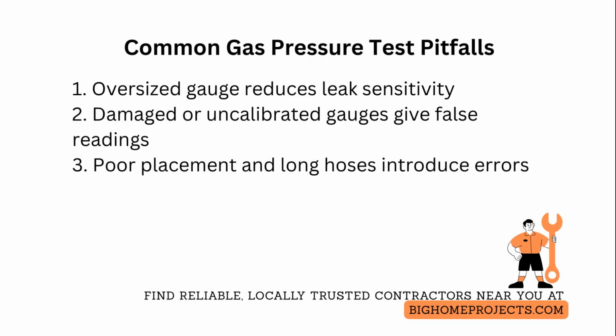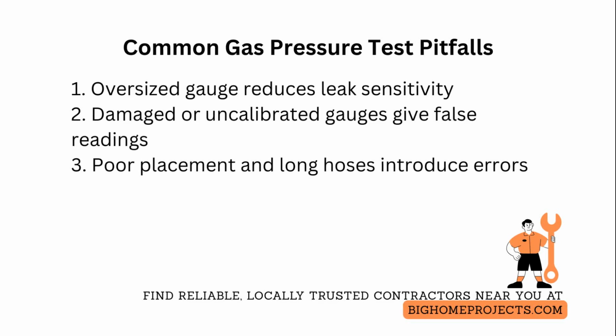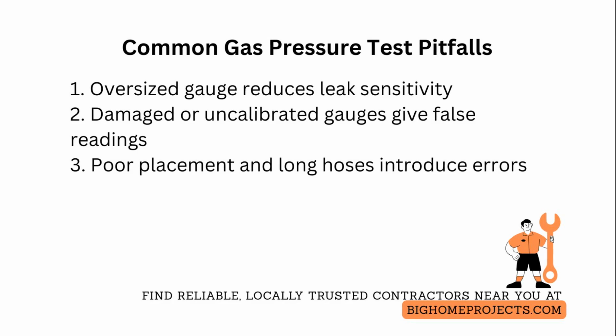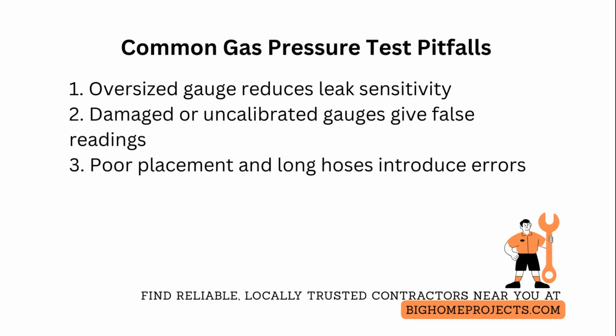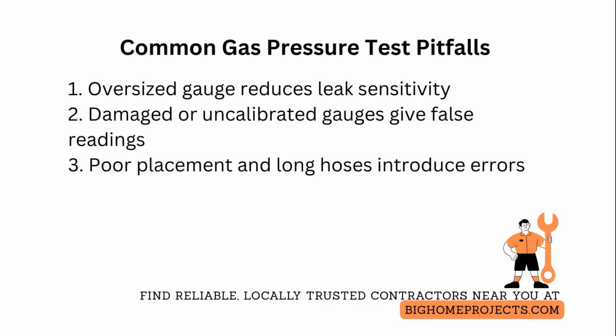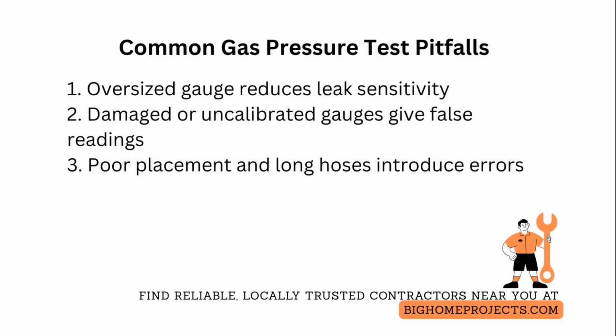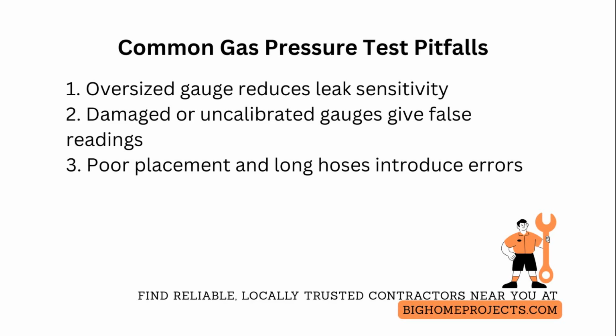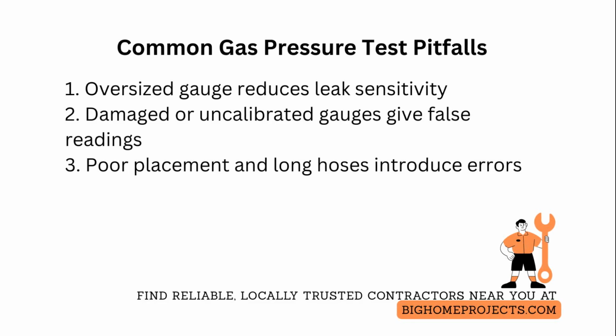One common issue is relying on damaged or uncalibrated gauges that give false stability. The remedy is to verify calibration against a reference standard prior to each test and keep calibration records. Another frequent error is poor gauge placement and long flexible hoses that introduce measurement lag and thermal expansion errors. Correct this by hard-plumbing a short, rigid connection to the test header and insulating the assembly from heat sources, so readings reflect system leakage, not conduit artifacts.